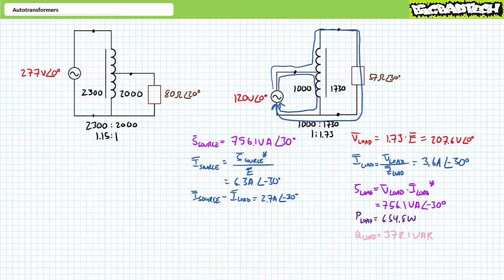In a step-up configuration you get two loops of current, both traveling clockwise. The low-voltage, high-current primary includes both paths at 6.3 amps at negative 30 degrees, whereas the high-voltage, low-current secondary side includes the 3.6 amps at negative 30 degrees drawn by the load.